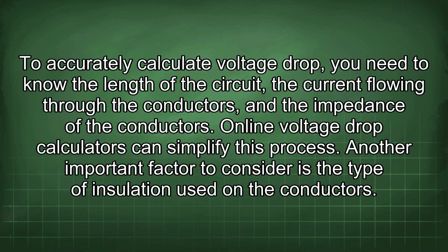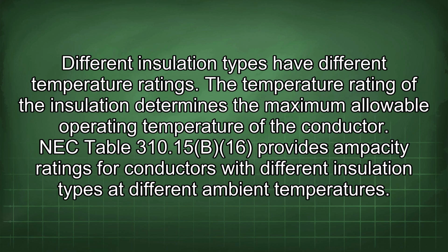Another important factor to consider is the type of insulation used on the conductors. Different insulation types have different temperature ratings. The temperature rating of the insulation determines the maximum allowable operating temperature of the conductor. NEC Table 310.15(B)(16) provides ampacity ratings for conductors with different insulation types at different ambient temperatures.